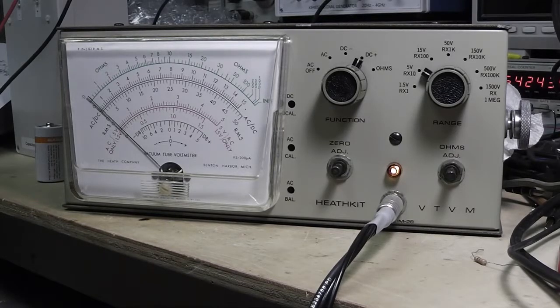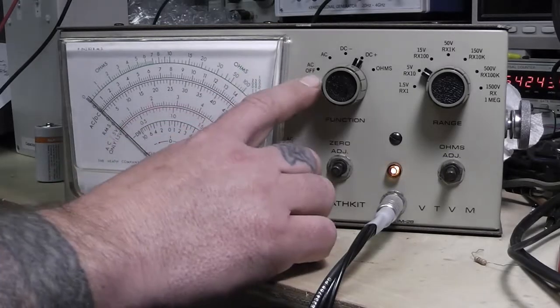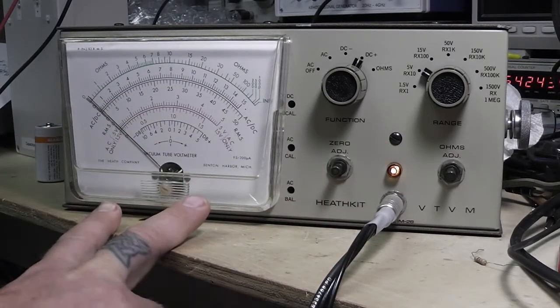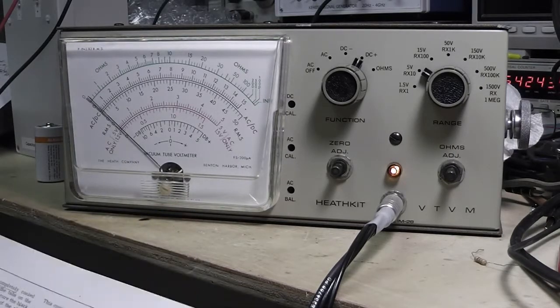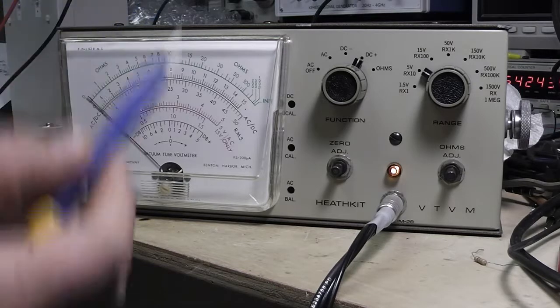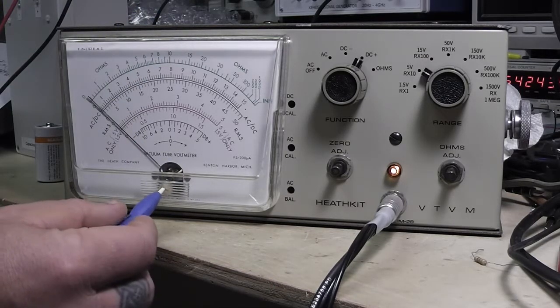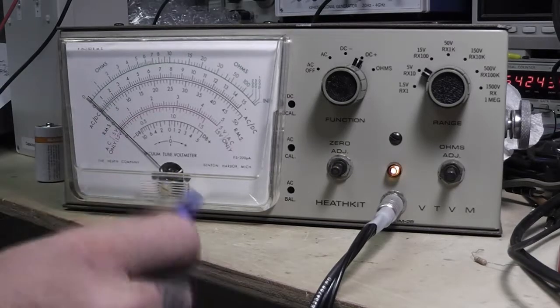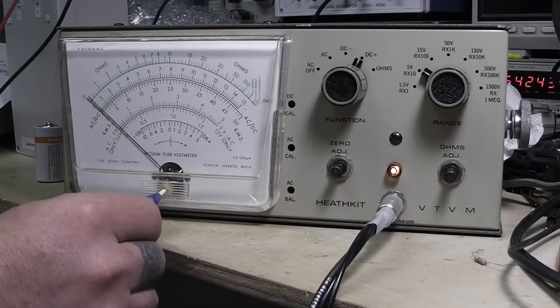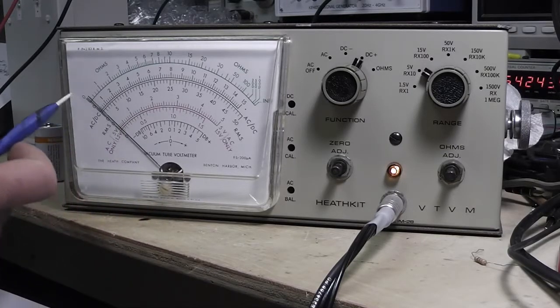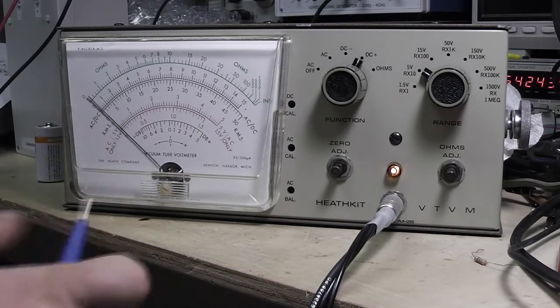The first thing we're going to talk about is, before you do all this, it says right here in the alignment procedure, turn the instrument off and make sure it's unplugged from the AC line. Make sure it's in the off position over here, because that shorts out this meter. The terminals behind it get shorted out. Then it says take a plastic screwdriver and put it in here and adjust this, which I've already done. I've got it on right now, but with it off, you adjust this very carefully right here in the front till you get this resting right at 0. Get down, look at it straight on, and make sure that's right at 0.